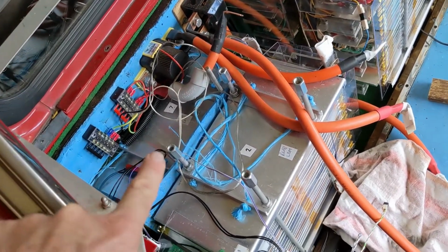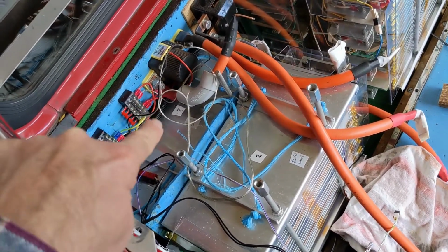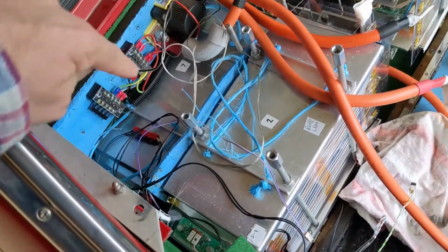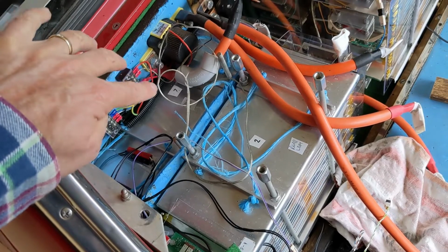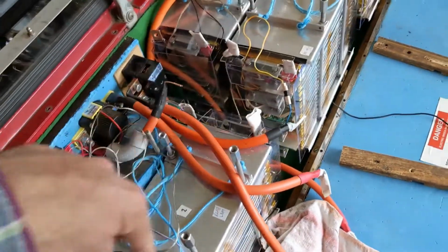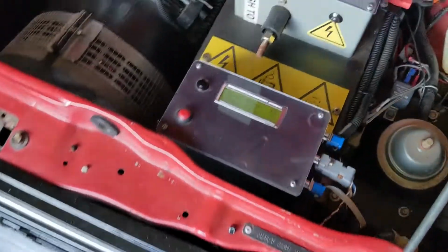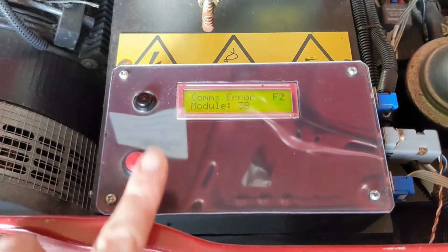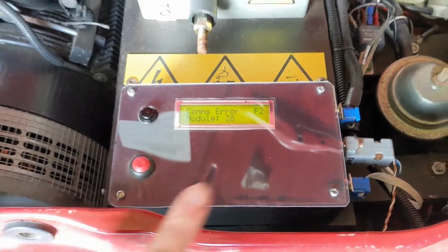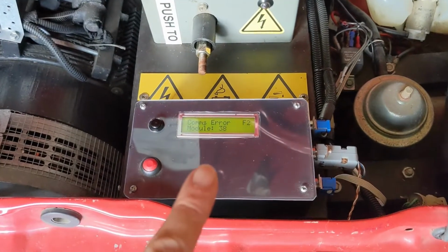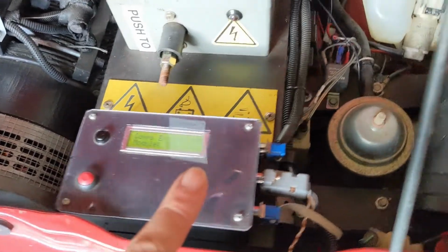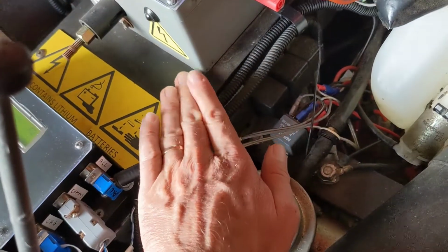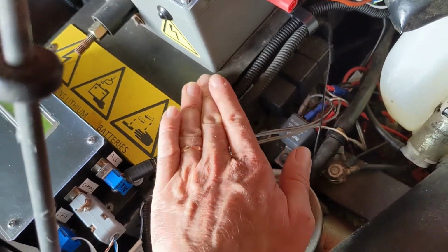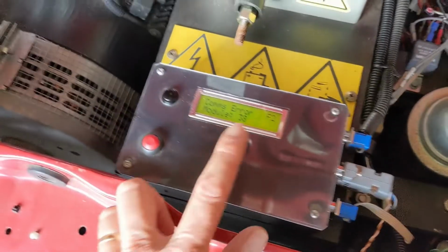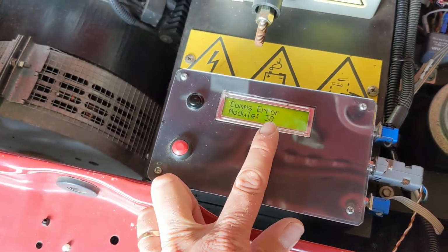The commands coming from the front aren't reaching here, and so this first one here that isn't getting the information from the master will say, hey, there's something wrong, send it on, send it on, send it on, and sends it all the way around, which means we come back here and we'll have a fault on the master unit, fault 2, and it's saying module 38. If you count up all of those cells that are still in the loop, there are 38 of them. The ones that are not in the loop are the ones in this box here, and there are 5 of them in there. So 39 to 43 are in that one. So the way you interpret that is module 38 has a problem.